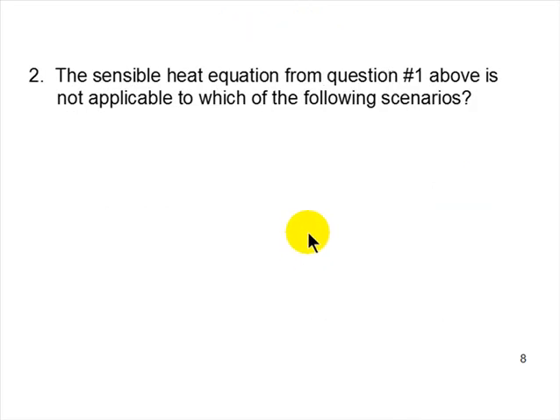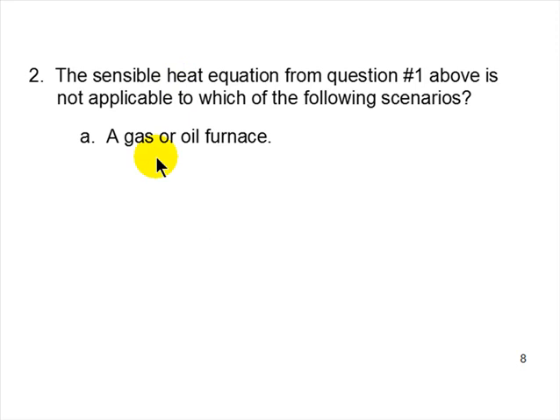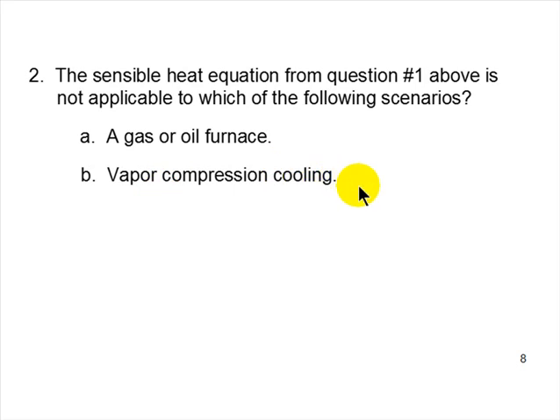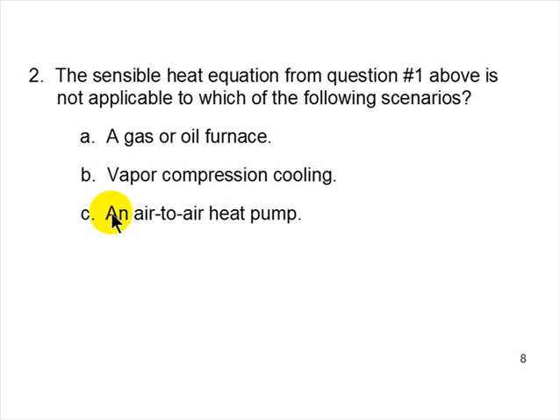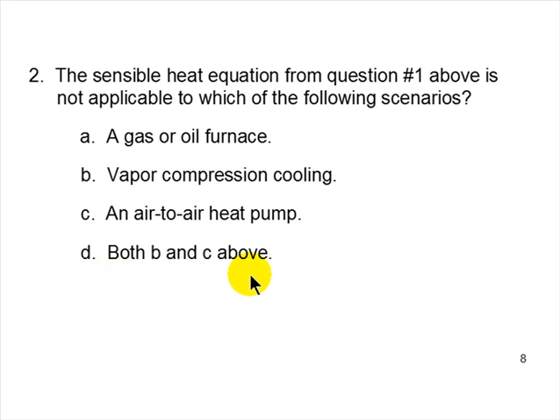Question 2: The sensible heat equation from question 1 is NOT applicable to which scenario? A) gas or oil furnace, B) vapor compression cooling system, C) air-to-air heat pump, D) both B and C. Answer: D — both B and C. Any vapor compression system using a compressor cannot use this formula because you cannot separate sensible from latent heat.